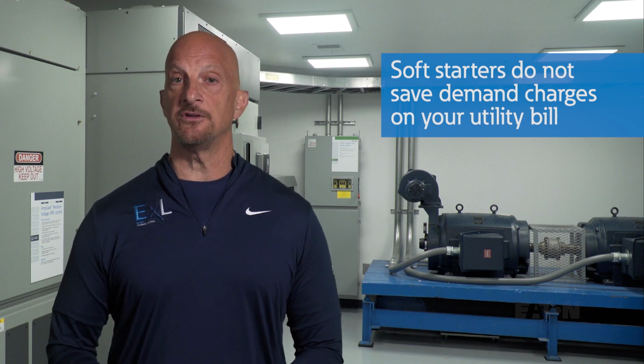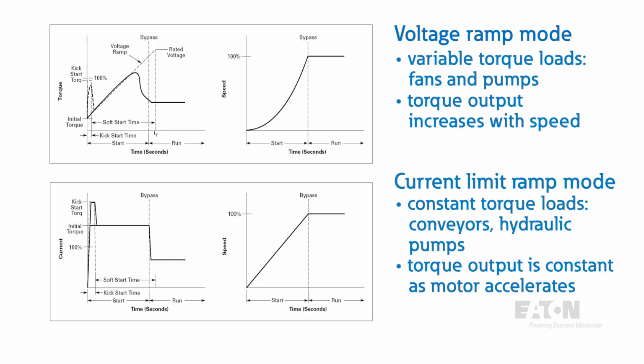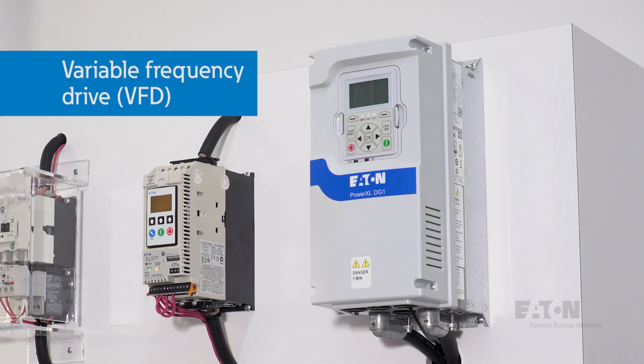This is a common misconception to be aware of. There are several key settings on a soft starter, and it's important to understand how those settings affect the starting time and the inrush current. Finally, a variable frequency drive offers a more refined soft starting capability as well as the opportunity to control the speed of the motor after starting.